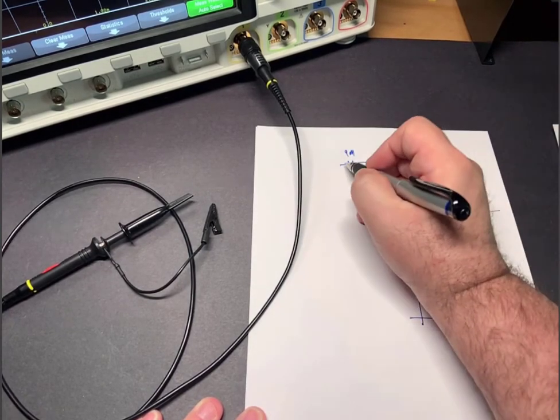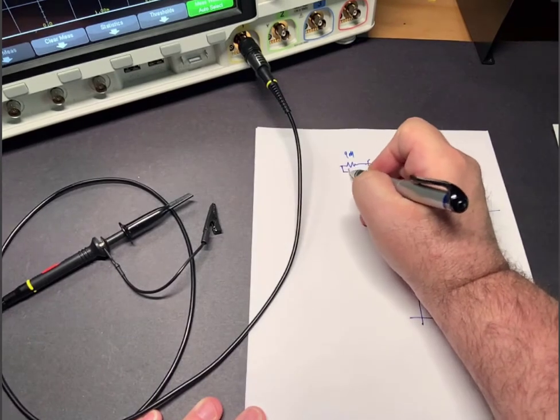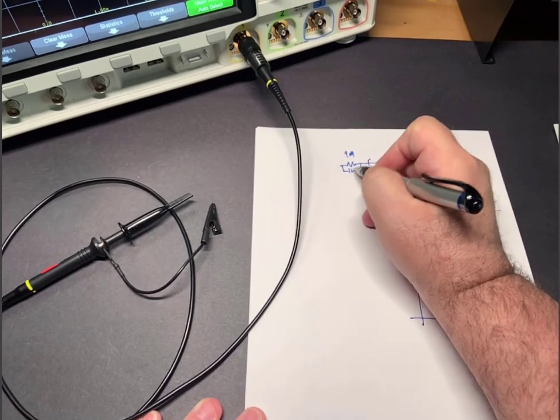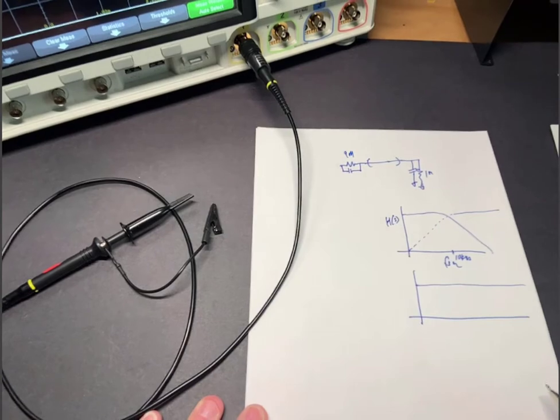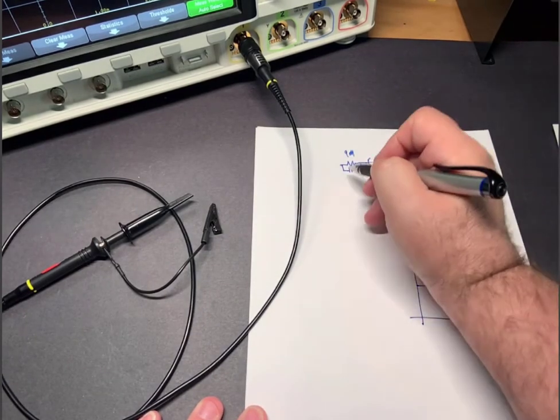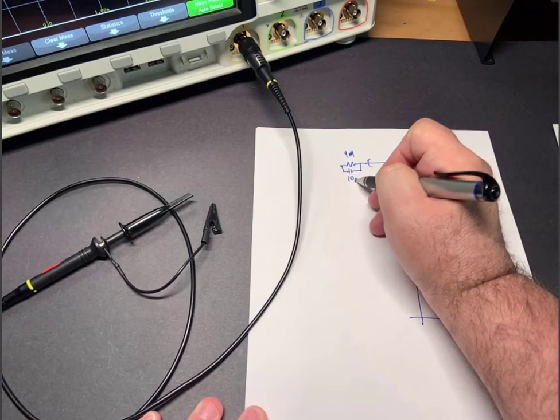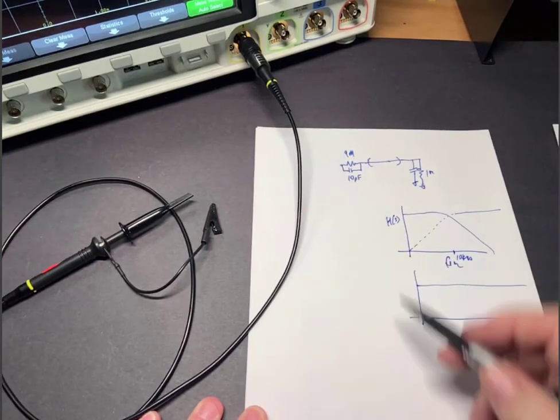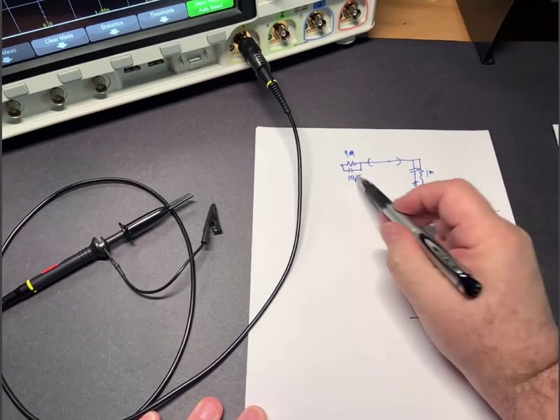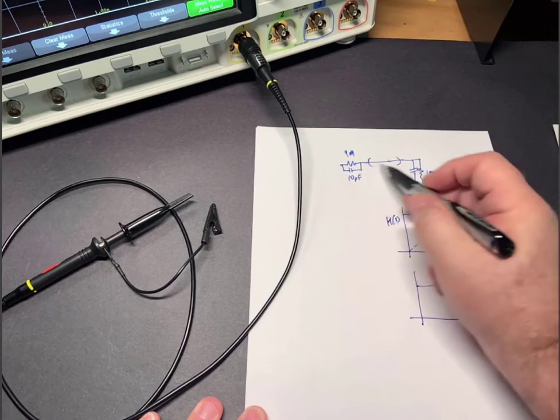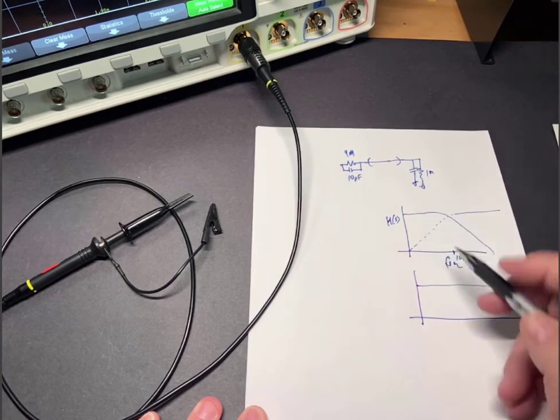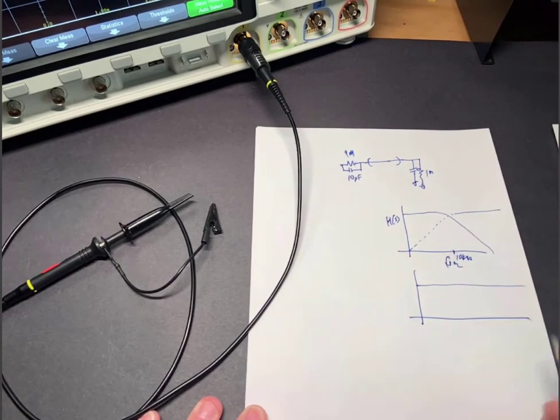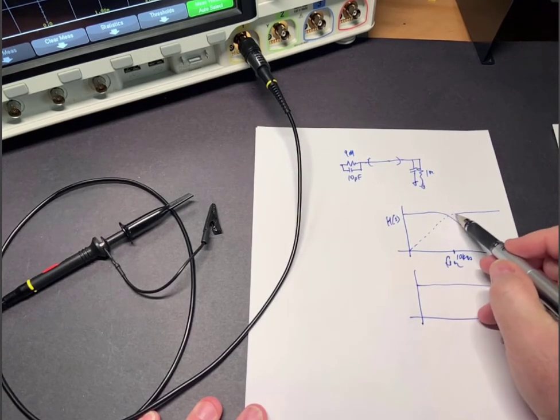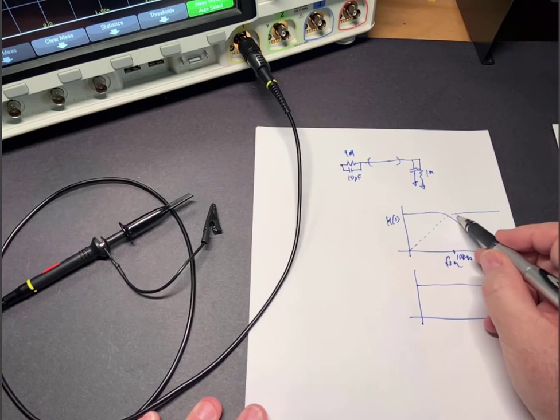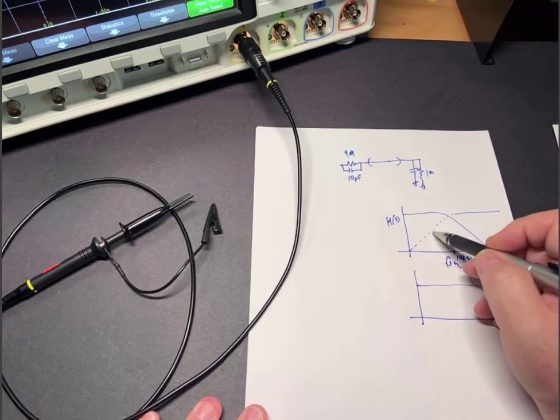And the way we do that is really simple. We add a capacitor in shunt across that 9 meg resistor at the front. And this is on the order of about 10 picofarads. And now, the combination of this 10 picofarad capacitor in series with the cable and the input impedance now represents a high pass filter.